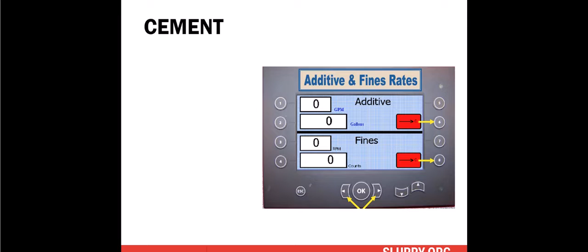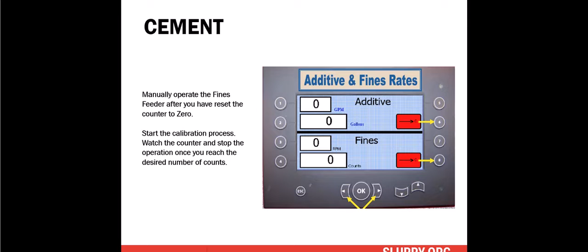Okay. Again, we're staying consistent with the screen of this particular machine. Different manufacturers have different configurations, and their operator's manual should define this process very clearly. We're going to manually operate the fines feeder. We're going to reset our counter to 0. We're going to start the calibration process. We're going to watch the counter and stop once we reach our desired number of counts. We're going to talk about that here in detail.